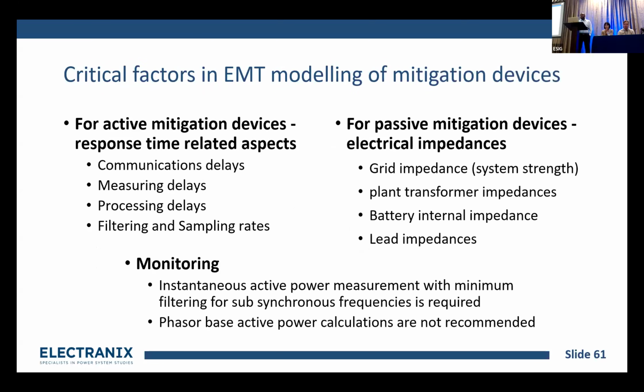So, critical factors in EMT modeling. There are two categories we can use to classify these mitigation methods. One is actively measuring and injecting power. The other is physics-based, the impedance-based methods that automatically inject power based on the phase angle jumps.